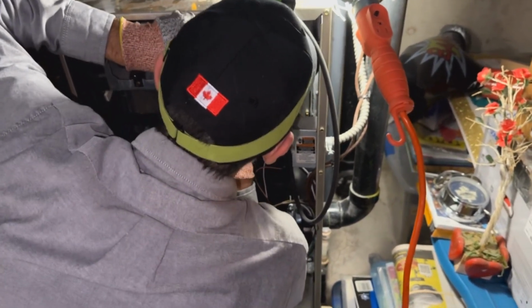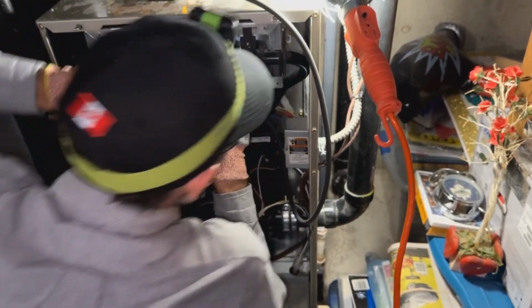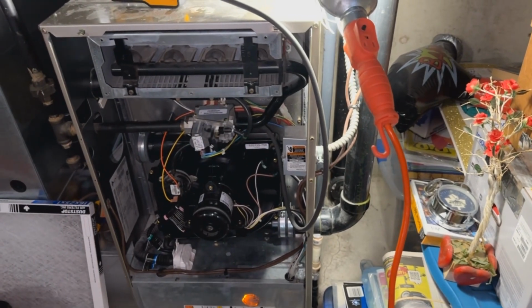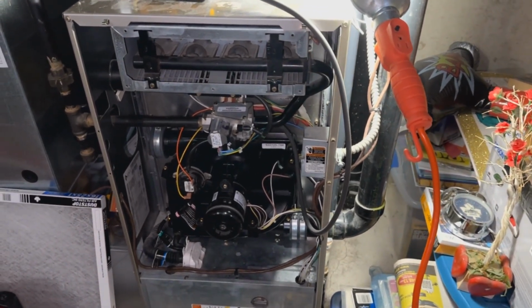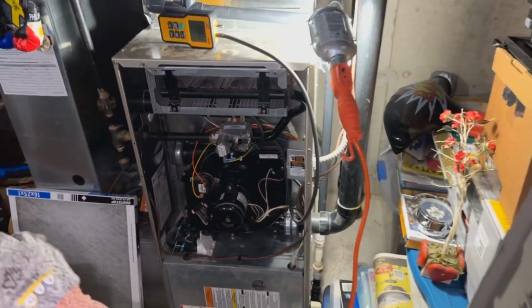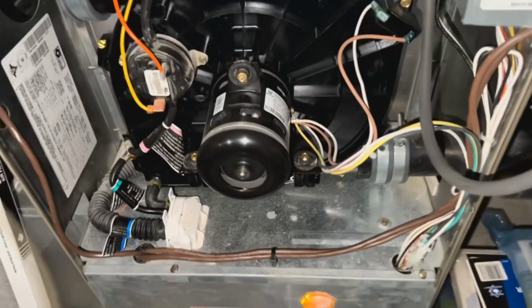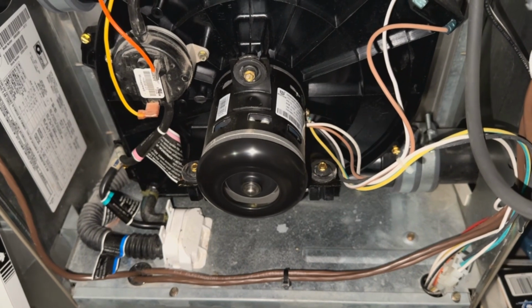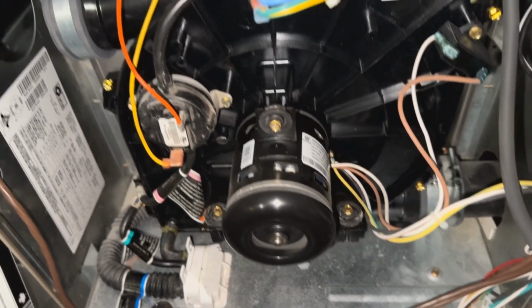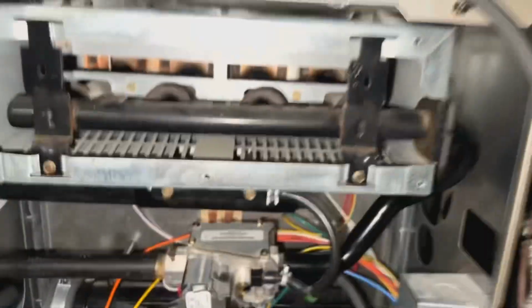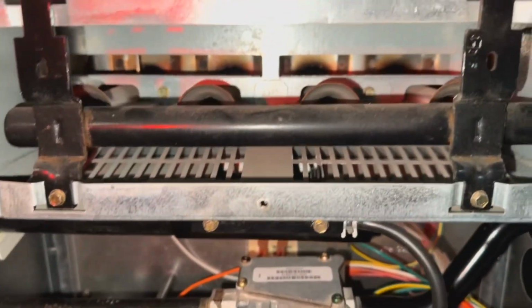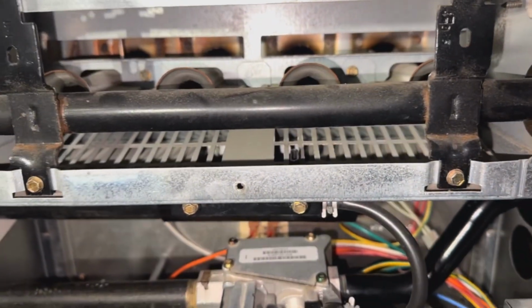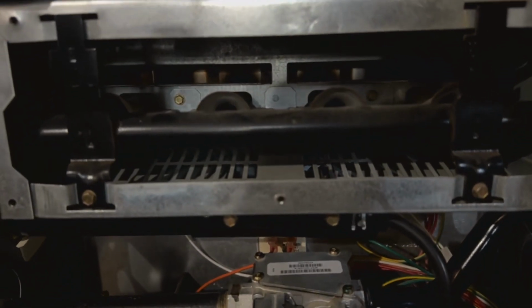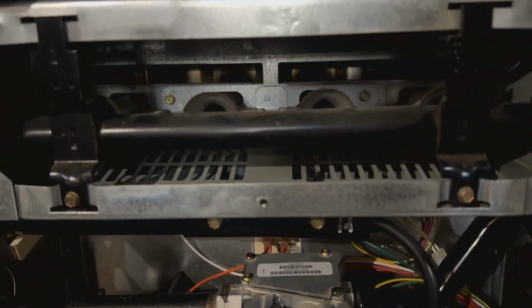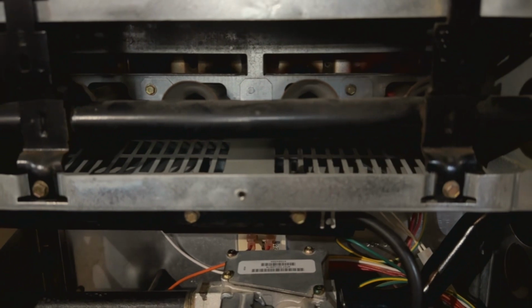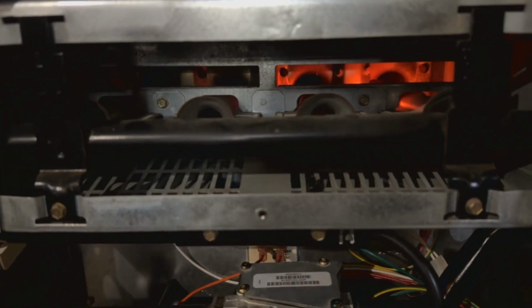Did your coil freeze up at one time? Yeah, when it was leaking. Did it? Yes, that was a little bit of rust in there then. Oh wow, that was a long time ago. Was it? So as you see now, the venter motor kicks on. That switch will be closed, and then you will see a nice orange glow, followed by a blue flame, if it's burning clean. If not, we could see a lot of orange in there.